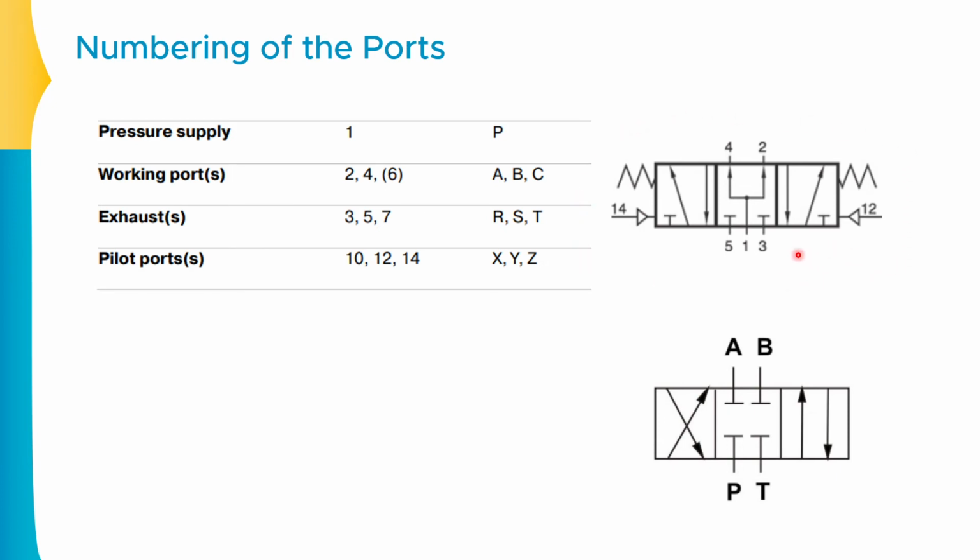So in this specific valve, what will happen? The normal position will always be the center position. And as you can also observe, the notations are written on the center part. So this specific position is known as the normal position of the valve. Now, whenever you want to actuate the side available at the left hand side of the normal position, you have to actuate this number 14 pneumatic side. Okay, so you have to pressurize this side. So what will happen? This position will get actuated.